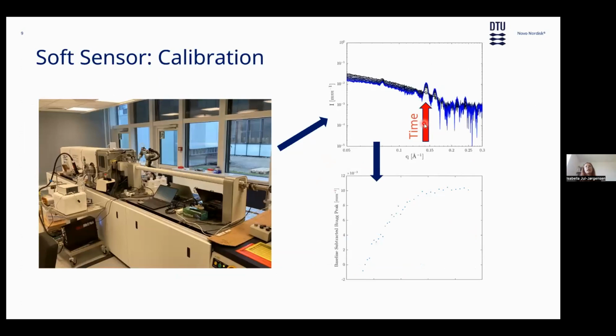So the first part was then to make a calibration, because what you really check after crystallization is whether the amorphous has transformed into crystals. So we needed reference values. So we had a setup with a SAXS machine, so a small angle X-ray scattering, and you can see that we did a small flow through setup with the SAXS, and then we had the Blaze probe in the crystallizing solution there. With the SAXS, it's very nice because you will get these Bragg peaks when you start having crystals, and then we can use those as a reference value. So you can see how these Bragg peaks increase during the process.